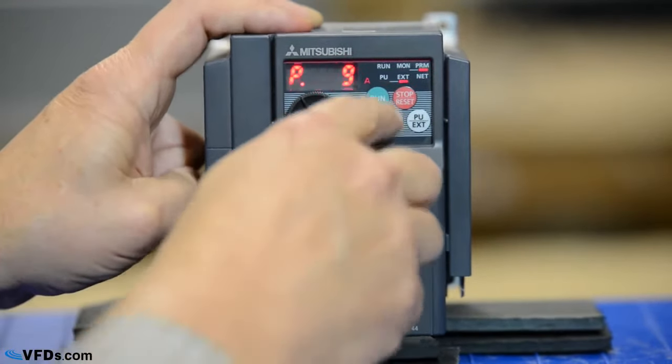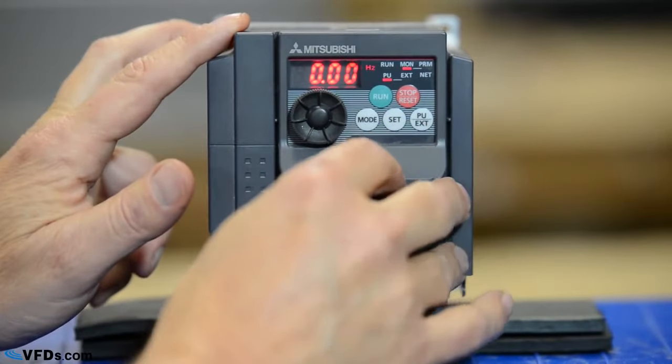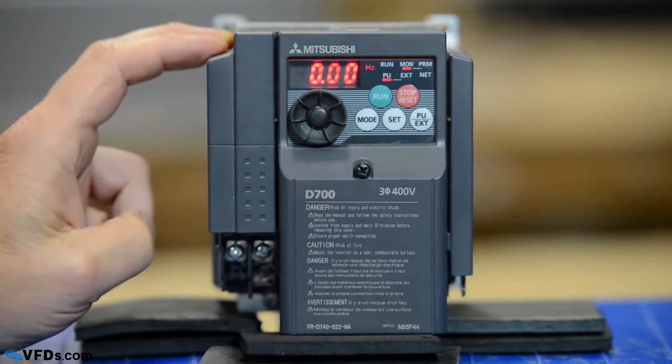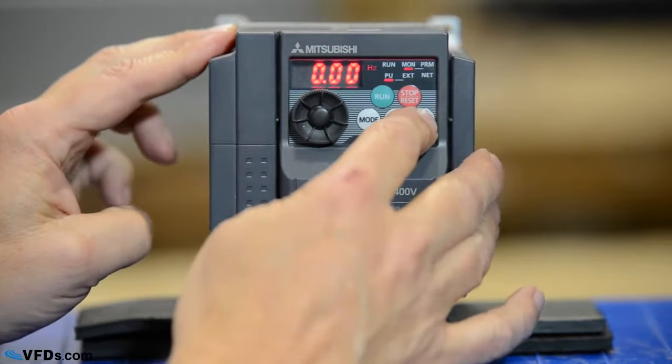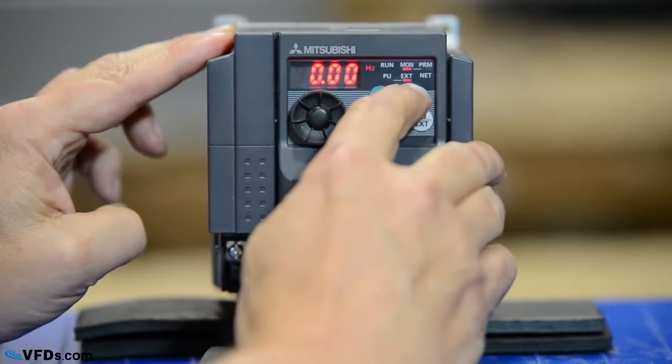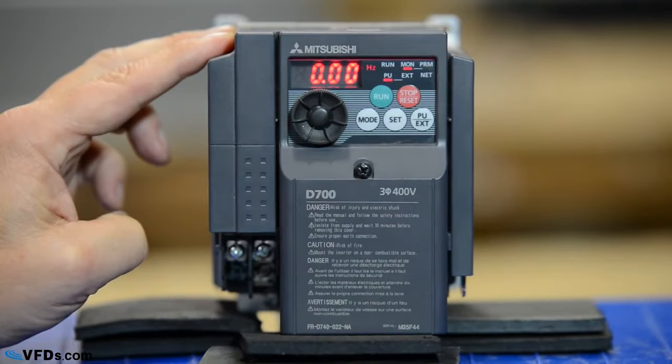Let's go ahead and run this drive. The first thing I want to do is make sure that I'm in the proper mode. Parameter unit allows me to run from the keypad. External allows me to run from different inputs. If I push this, you can see that I'm in parameter unit mode. Push it again, I'm in external mode. I want to be in parameter unit mode, so I'm going to toggle that back to parameter unit mode.